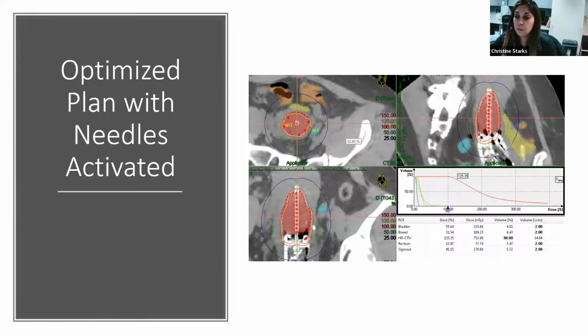Another tool within OnCentra is using the dwell position selector. As you can see out laterally, you can choose which dwell positions you need to obtain coverage and then manually increase those dwell times. Remember, each dwell position is 5 millimeters apart. So it's beneficial as you're optimizing to choose at least 2 dwell positions so that you can either spare the organ at risk or increase the dose to that area.